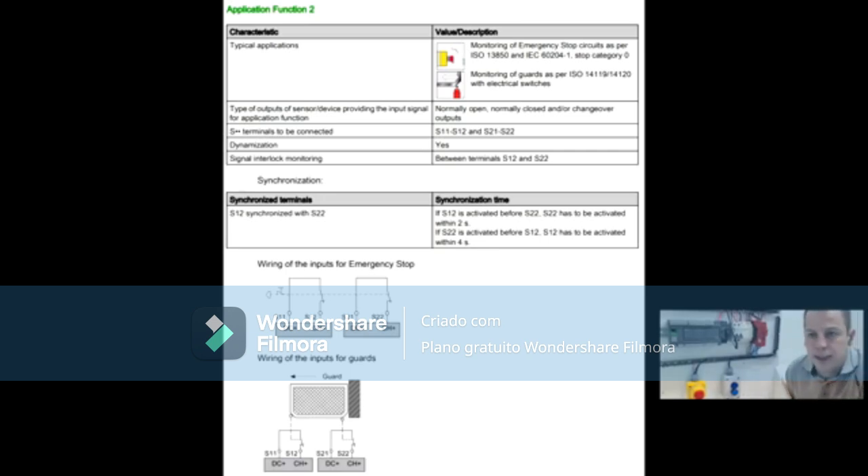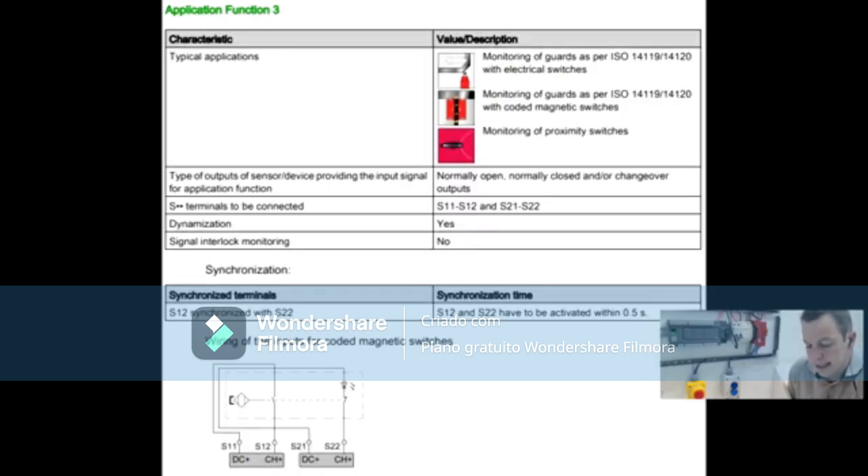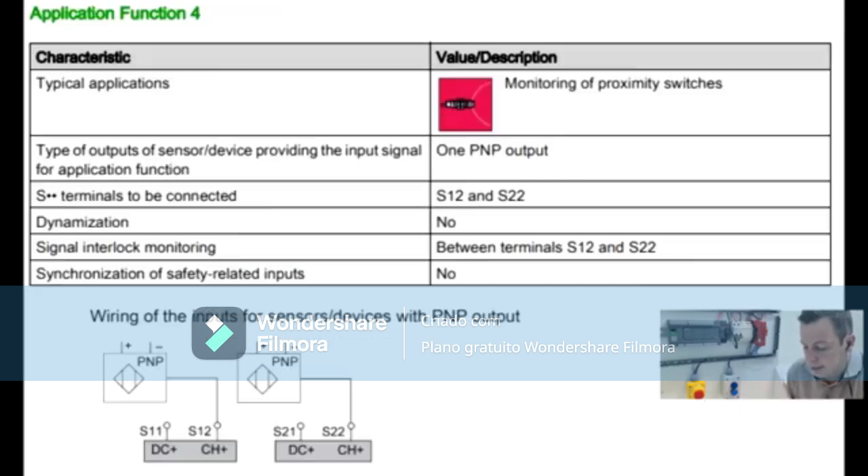What if S22 fires first? Then you have four seconds to activate S12. It sounds a bit unusual but there are applications that need this synchronization window. Function 3 uses the same contacts but with synchronization and with dynamization, and the synchronization between contacts must be less than half a second — it doesn't matter which fires first, S12 or S22. It can even be used for a two-hand control in some applications.